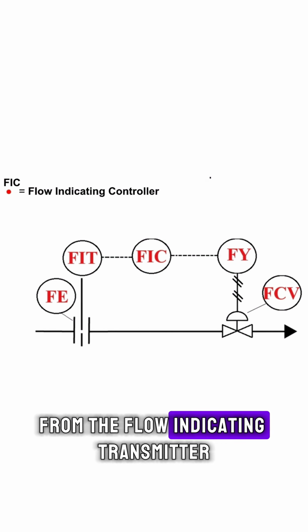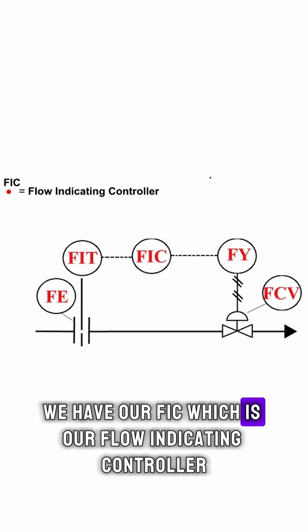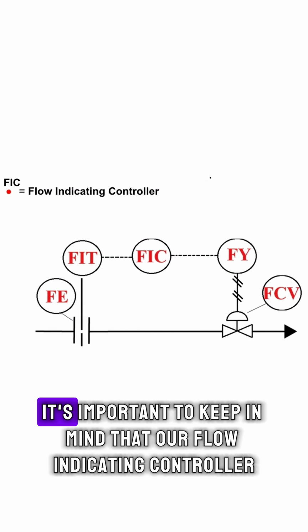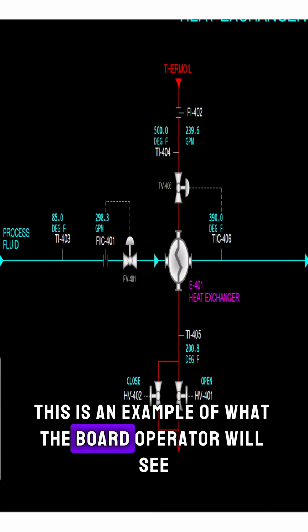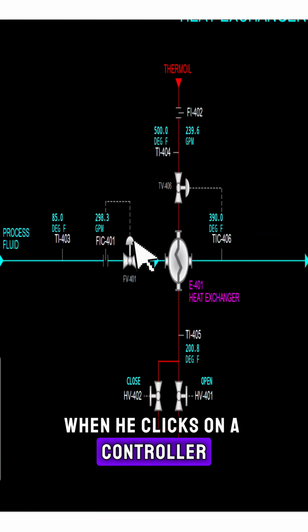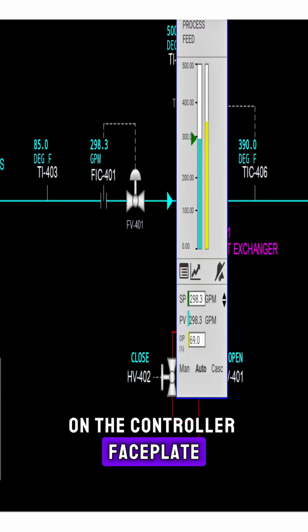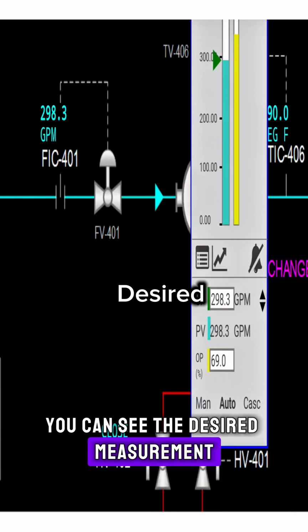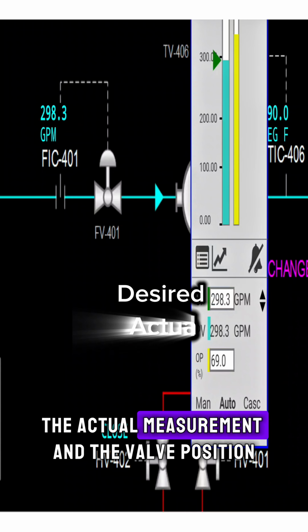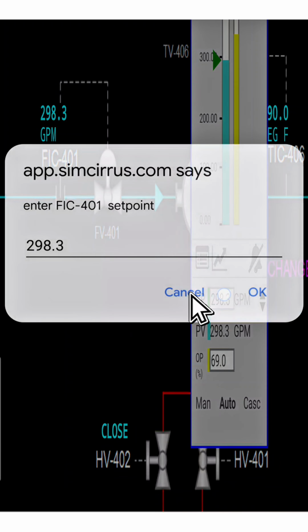From the flow indicating transmitter, we have our FIC, which is our flow indicating controller. It's important to keep in mind that our flow indicating controller is located on the board. It's not something you can physically see in the field. This is an example of what the board operator will see. When he clicks on a controller, the controller's faceplate pops up. On the controller faceplate, you can see the desired measurement, the actual measurement, and the valve position.